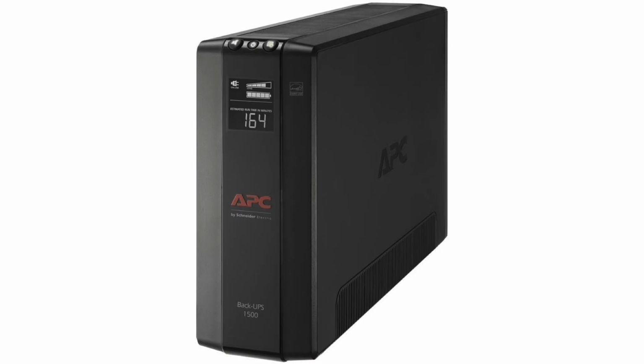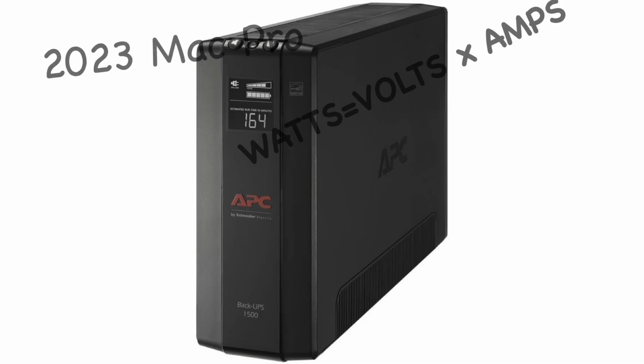So, a little bit more math. That 2023 Mac Pro is 330 watts when it's firing on all cylinders, assuming 120 volts US mains power, plugged into the APC whatever 1500, which is rated at 1500 VA, the industry unit volt-amperes, not to be confused with watts, since watts are volts times amps, and that'll run that Mac Pro for... what was I asking?